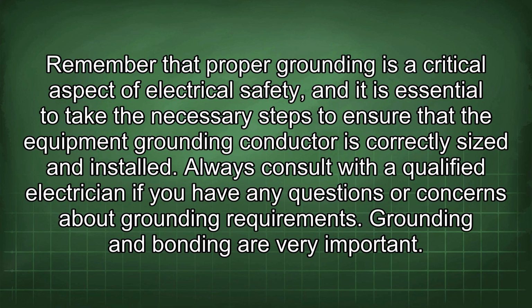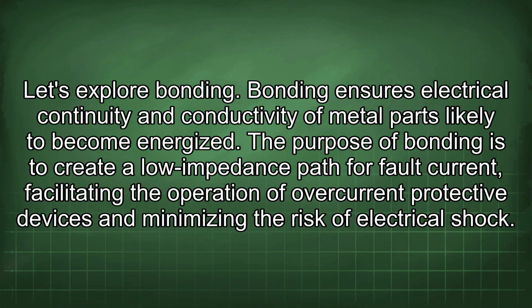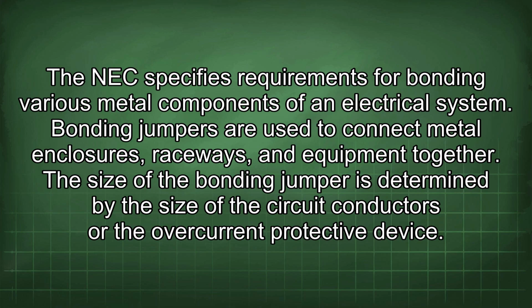Grounding and bonding are very important. Let's explore bonding. Bonding ensures electrical continuity and conductivity of metal parts likely to become energized. The purpose of bonding is to create a low impedance path for fault current, facilitating the operation of overcurrent protective devices and minimizing the risk of electrical shock. The NEC specifies requirements for bonding various metal components of an electrical system.